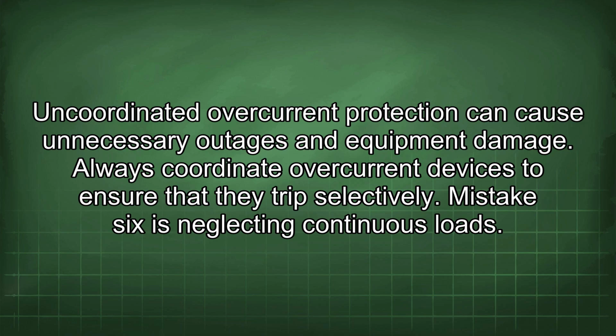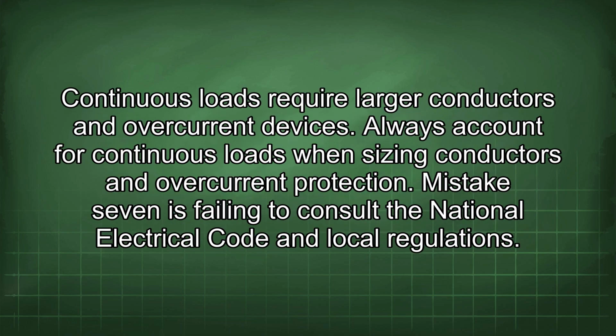Mistake 6 is neglecting continuous loads. Continuous loads require larger conductors and overcurrent devices. Always account for continuous loads when sizing conductors and overcurrent protection.